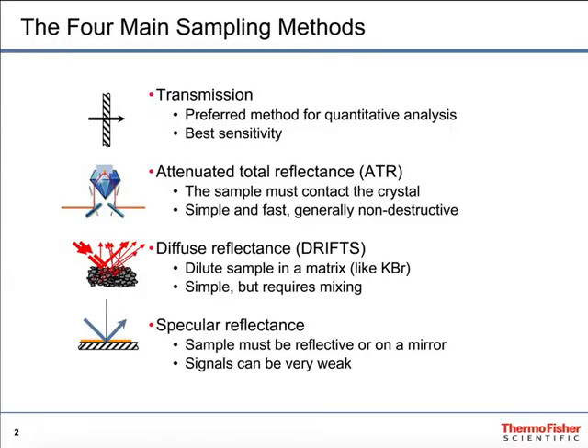The first of the four techniques is transmission, in which the IR beam passes through the sample and onto the detector. In attenuated total reflection, the IR beam enters a crystal, interacts with the sample which is on the surface of that crystal, then exits the crystal and passes onto the detector.